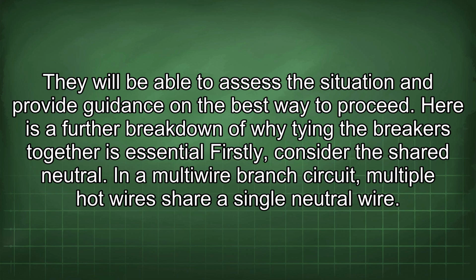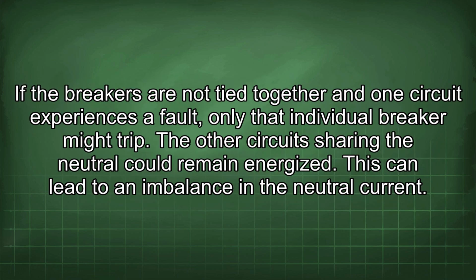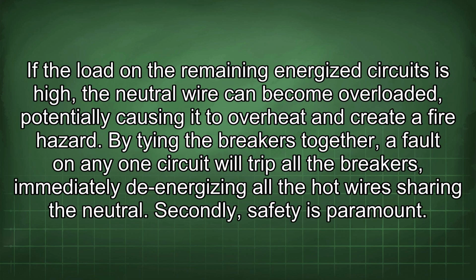Here is a further breakdown of why tying the breakers together is essential. Firstly, consider the shared neutral. In a multi-wire branch circuit, multiple hot wires share a single neutral wire. If the breakers are not tied together and one circuit experiences a fault, only that individual breaker might trip. The other circuit sharing the neutral could remain energized. This can lead to an imbalance in the neutral current. If the load on the remaining energized circuits is high, the neutral wire can become overloaded, potentially causing it to overheat and create a fire hazard.